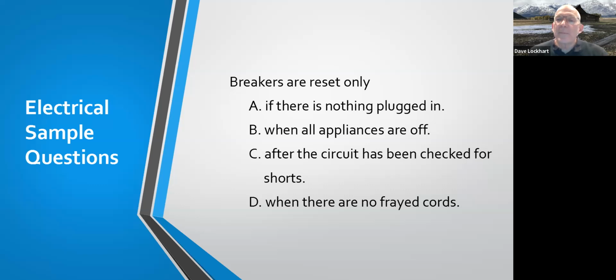Exactly. We're not going to be able to go around and get everything unplugged, but if we could check that circuit for no shorts on it, nothing shorted out to ground causing that breaker to trip, we would be cleared on that. And that's a quick, easy test to make sure. Granted, you may see some resistance on there due to the loads, but you definitely don't want to go into ground in a short. So great job.